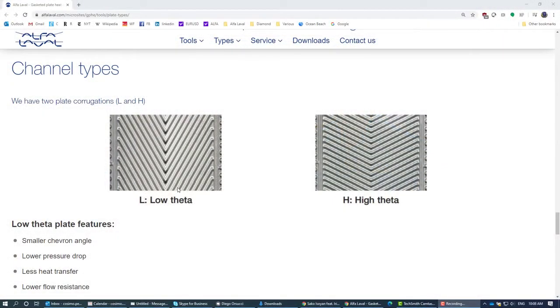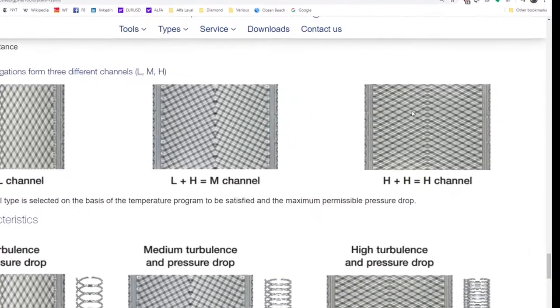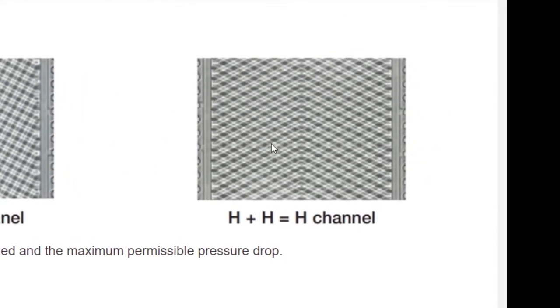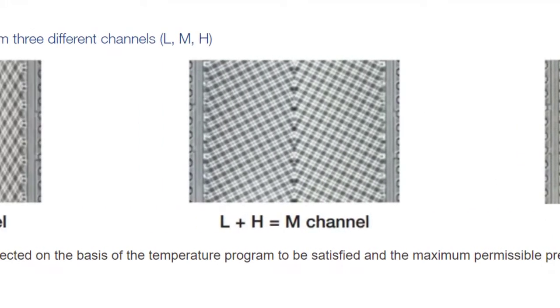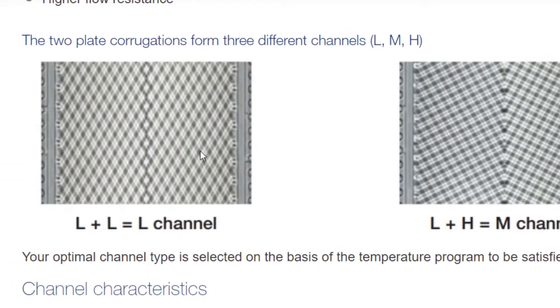The heat transfer area of a plate can have many patterns pressed into its surface depending on the duty. However, the most common type is the chevron pattern. There are two commonly used chevron angles which are referred to as high or low theta. Theta refers to the openness of this angle. A wide angle plate is a high theta plate, whereas a low angle plate is a low theta plate. When two high theta plates are placed together, more contacts are formed in the channel than when two low theta plates are placed together.